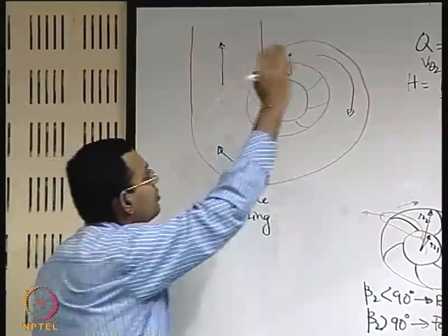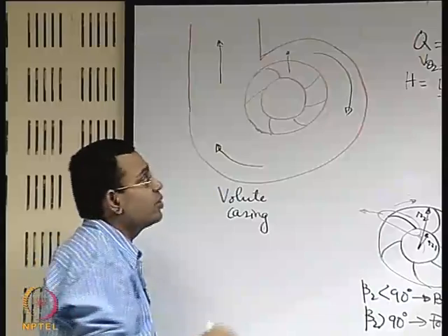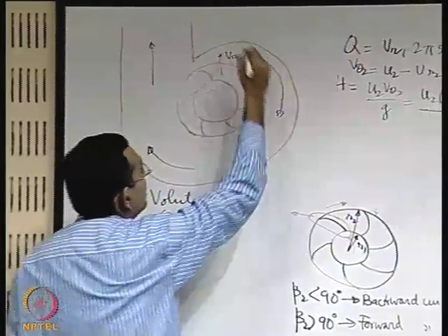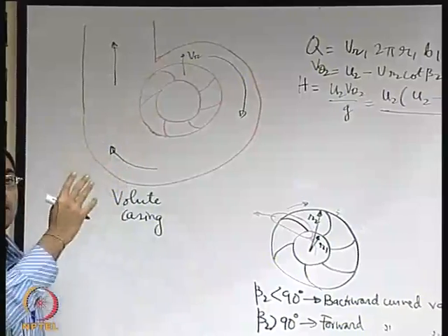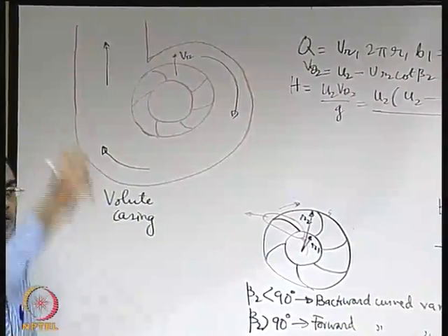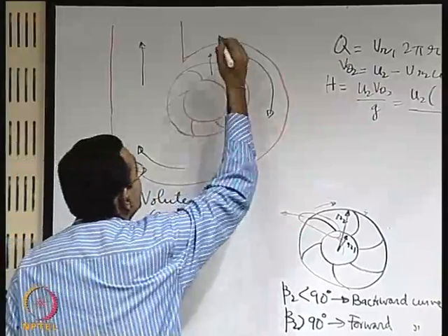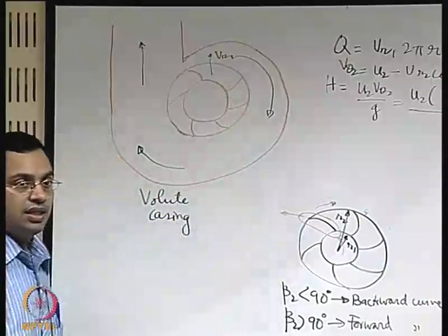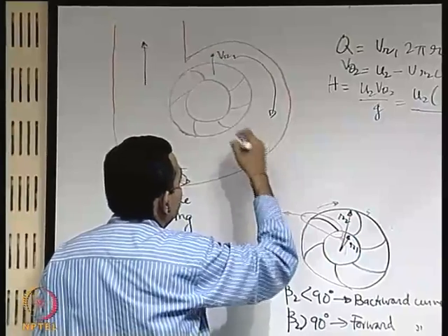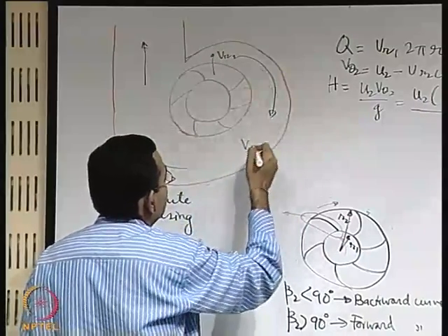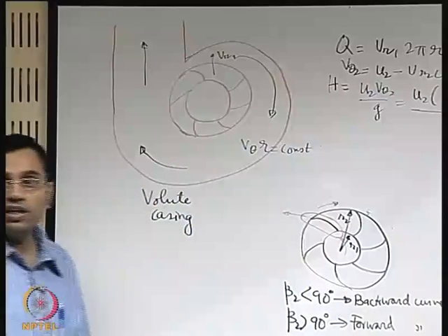So, in the volute casing, why should the shape be like this? The fluid enters with a constant radial velocity and exits the impeller with a constant radial velocity. That means it enters the volute casing with that radial component of velocity, say Vr2.